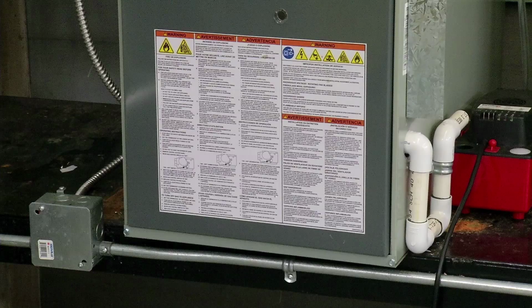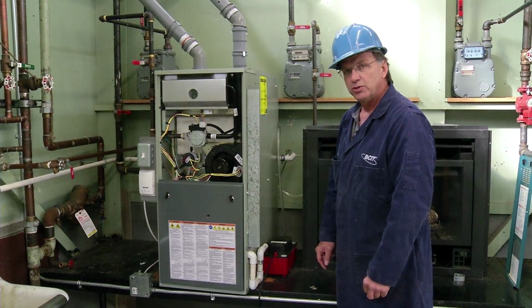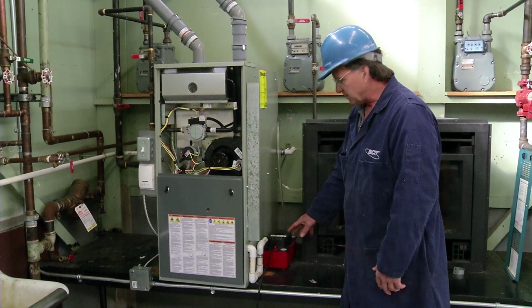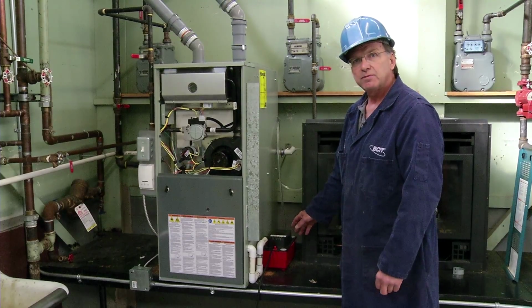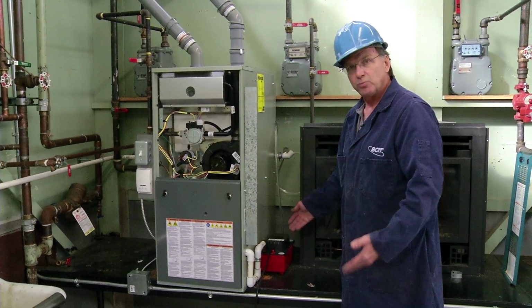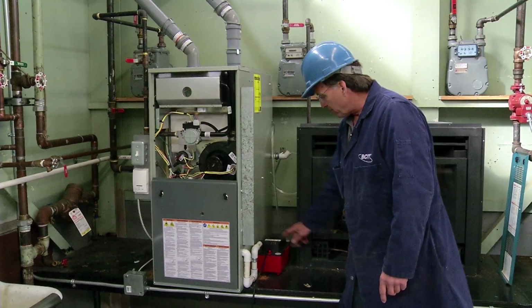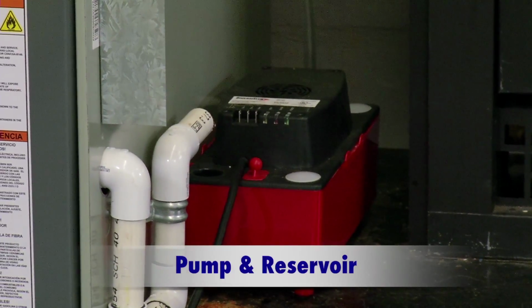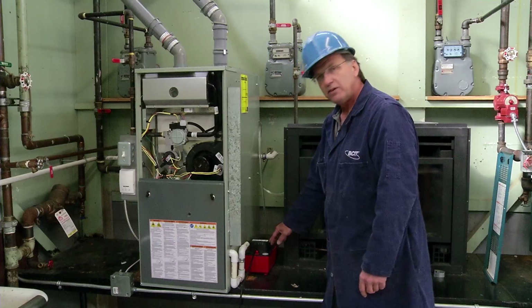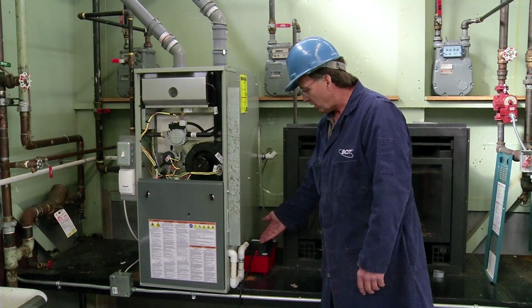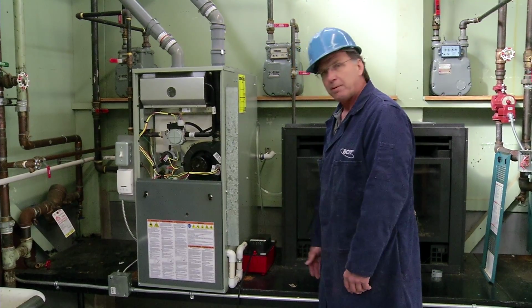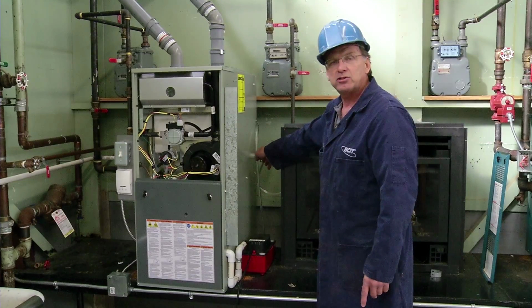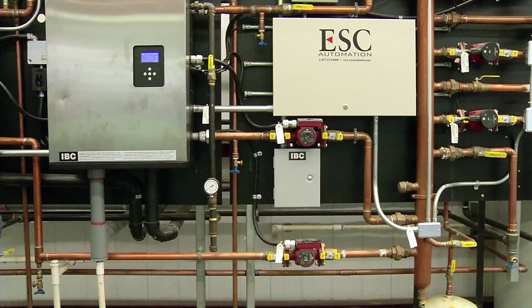One of the problems with the condensate, of course, is that it's coming out of these units by gravity, and sometimes we can't drain them by gravity because our drainage piping is below it. So they offer just a simple little pump and reservoir. We can drop that in. There's a float in there. When the reservoir gets filled enough, it'll just open up a pump, and we can pump that to a higher source and out of the house.